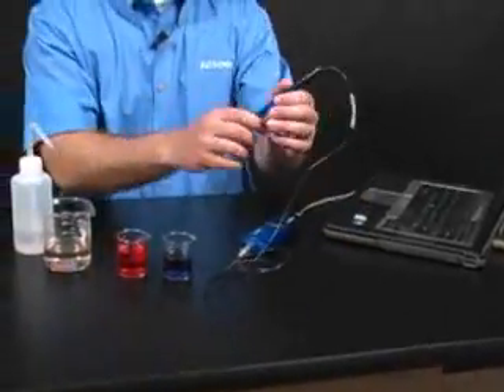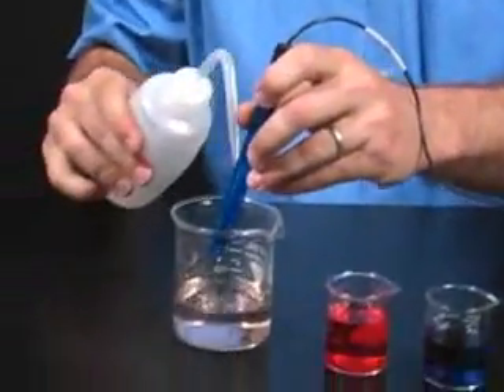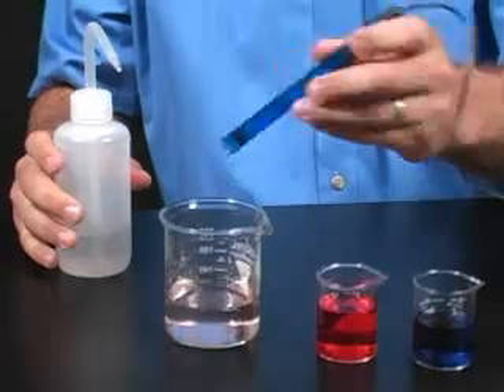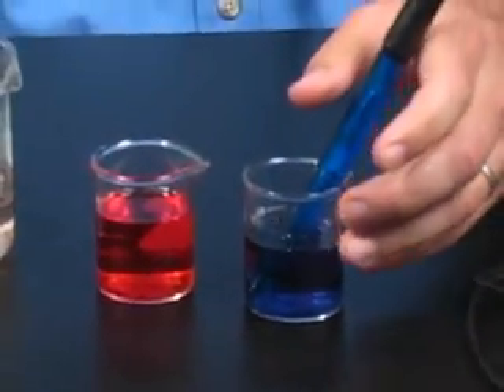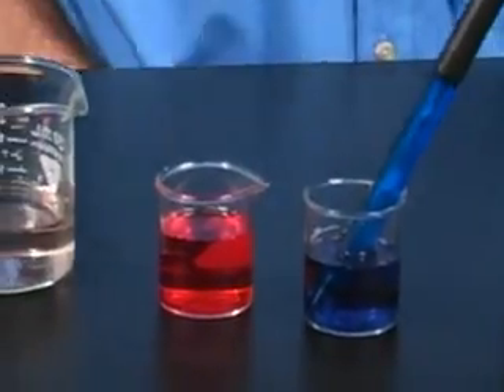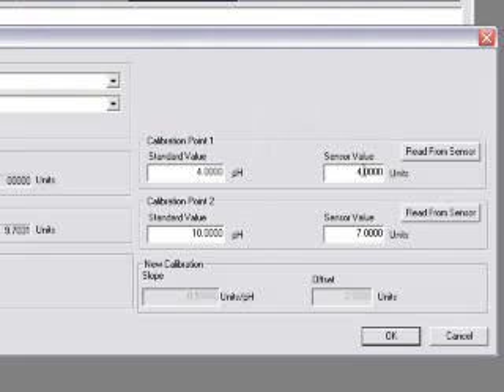Now, take the probe, remove it from the plastic storage bottle, rinse the probe, and place it in your first pH buffer solution. In this case, it's our blue pH 10 buffer solution. In the Calibrate Sensors window, click the button titled Read from Sensor in the box corresponding to that pH buffer solution. You'll notice that the value in the sensor value box has changed. This indicates that the current measurement of 9.7 is now associated with a pH of 10.